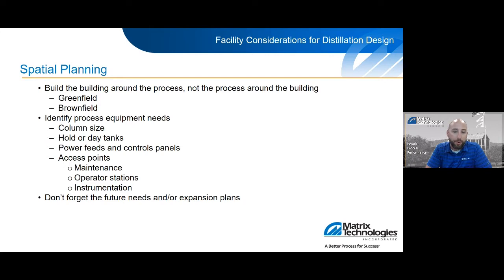How do you plan on storing your products? Does a column feed directly to a storage tank? Is it a day tank? Where do your power feeds come into the space, and how close do you want your control panels to the devices? Where your operator station is going to be located, and what type of access do you need? Do your platforms or mezzanines, are they required for your instrumentation or your valving access, or even access to the top of the tanks?